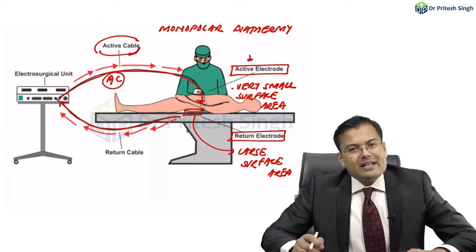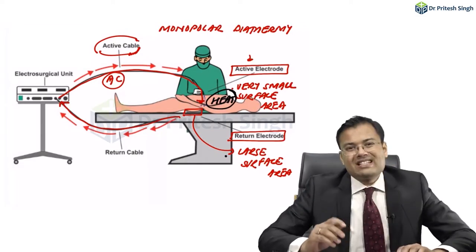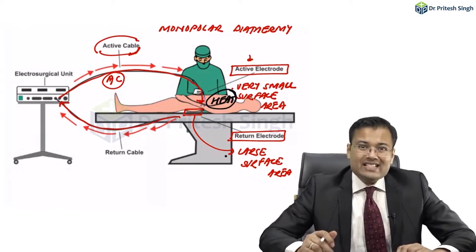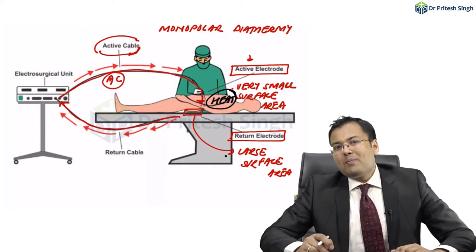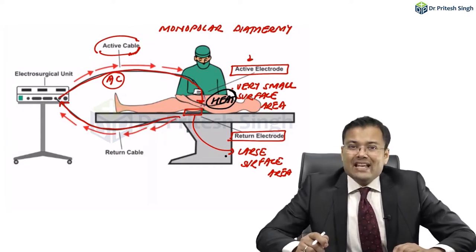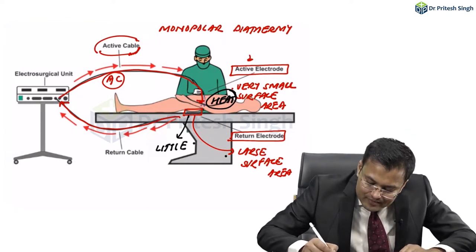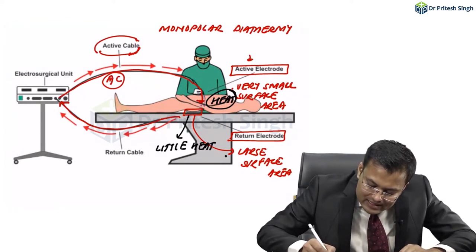Because of the very small surface area at the active electrode, concentrated electric current produces heat. In comparison, since the surface area is larger in the passive electrode, there is little heat production.